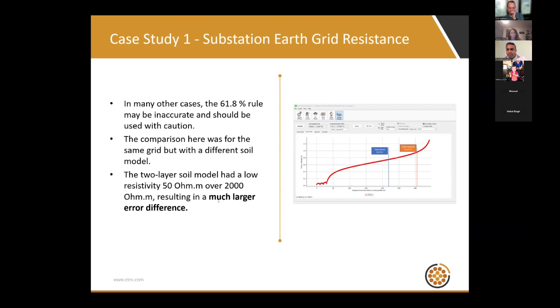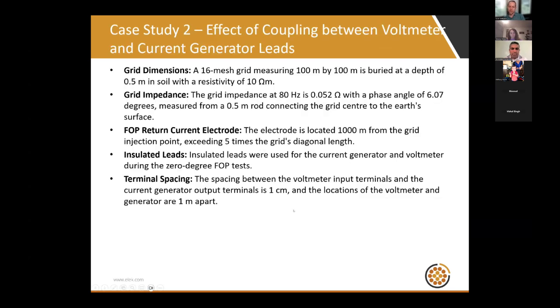We saw the first case study where we simulated a grid, changed the soil model and tested the 61.8% rule for apparent grid impedance. Case study two: let's consider the effect of the leads. In practical terms, when we do this test and we're injecting current, we run leads away from the grid to inject the current, at least 5 times the diagonal distance of the earthing system. So pretty far. And as we're measuring voltage, we also run leads.